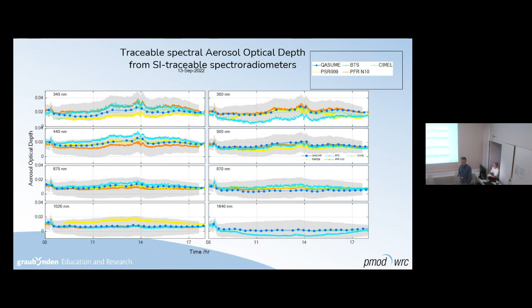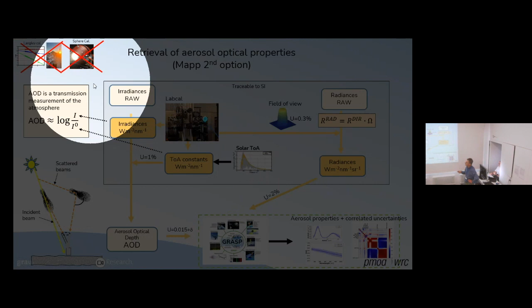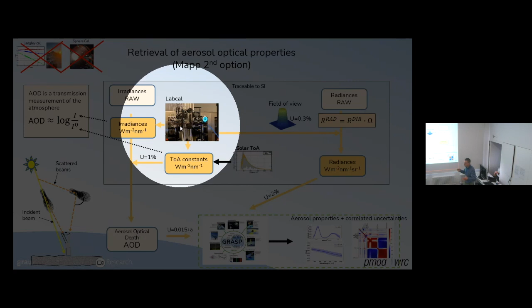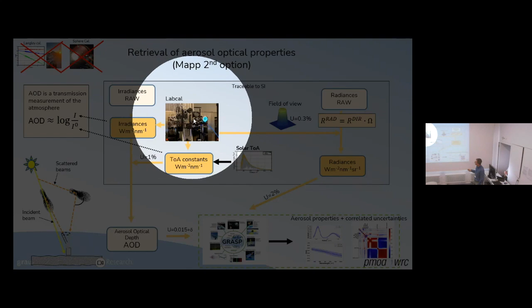Coming back to this scheme, there's the possibility that we can combine some of these calibrations and we can get rid of this sphere calibration, for example, and just rely on this primary lab calibration and somehow bring the irradiance calibration and the radiance calibration together. The information that we need for that is the field of view of the instrument. Basically, it's a solid angle. Then the conversion is actually very trivial. You see, it's really just a multiplication. From one calibration to the other, you can just swap between the two calibrations if you know your solid angle of the instrument. And so you can actually rely on a single calibration with a characterization of your instrument to try to also retrieve your aerosol properties.